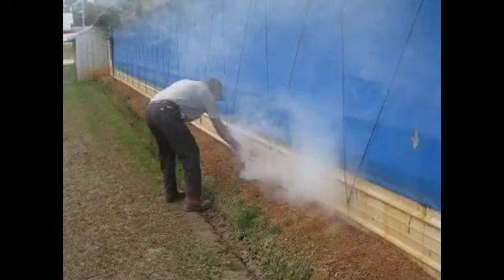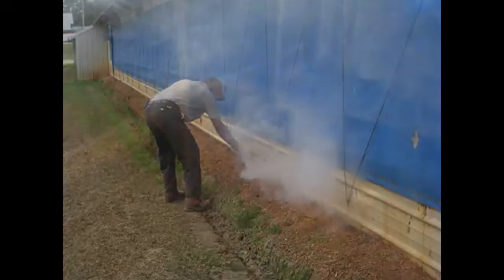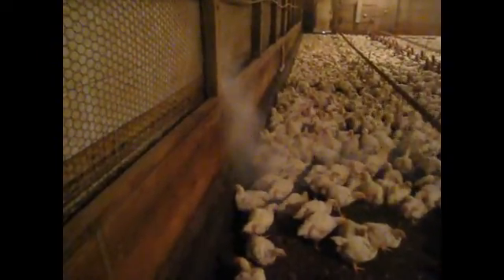Smoke testing the house while it's still in negative pressure mode will help you identify and locate areas where air is leaking into the building. Common places for air to leak into the building are around manned doors and end-wall doors, tunnel inlet and sidewall curtains, perimeter vents or attic vents, exhaust fan louvers, holes in the ceiling, and the joint between the concrete foundation and the lumber wall.